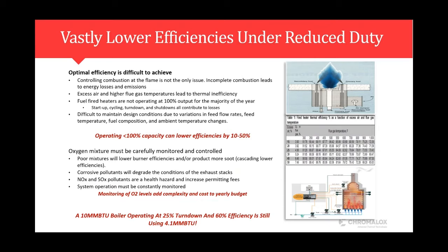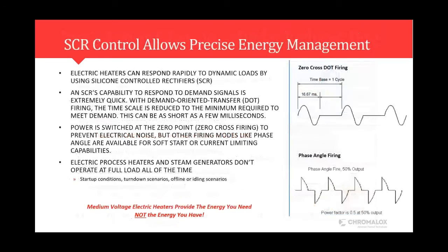So really the takeaway there is, if you're using a 10 million BTU boiler as an example, and you're operating it at 25%, because of that reduction in efficiency, let's say 60%, you might only need 2.5 million BTU, but in reality, you're still using 4.1 million BTU. So you're still using more energy than is required. On the electric side, if you need 2.5 million BTU, that 99% efficiency is going to get you using basically what you need at that point. So again, that factors into how these systems are controlled.